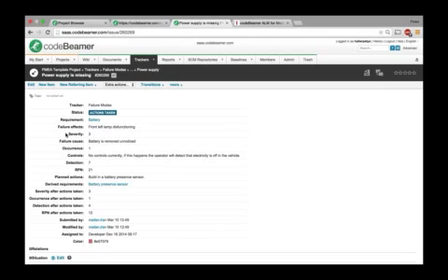We have these values like the severity, occurrence, and the detection. And this is the risk priority number here, which is the multiplication of these three values above: detection, occurrence, and severity. But we also have to define a failure cause and the controls, and then we will plan the actions and these values after the mitigation and the actions taken.